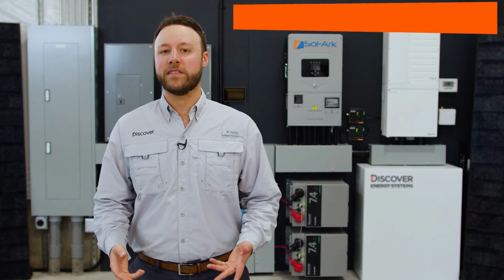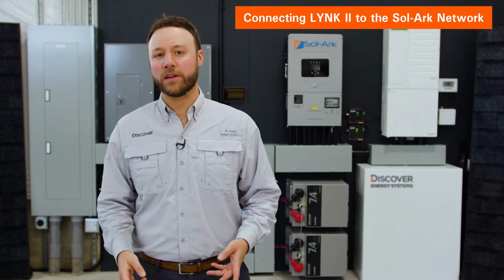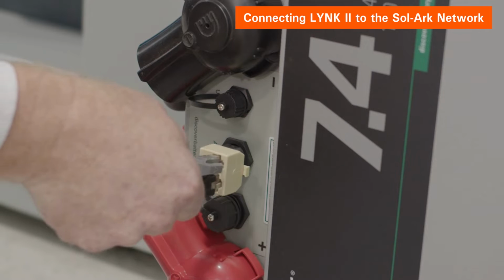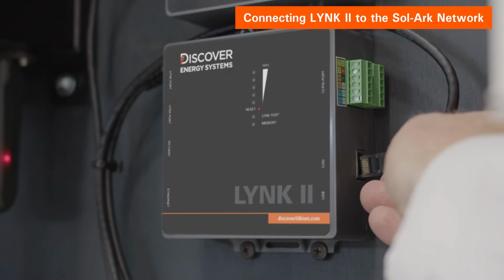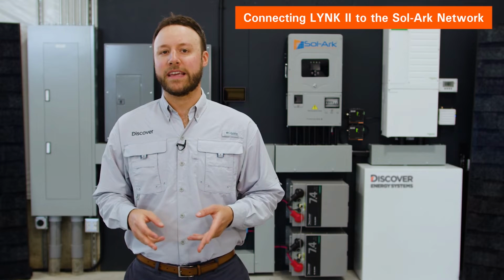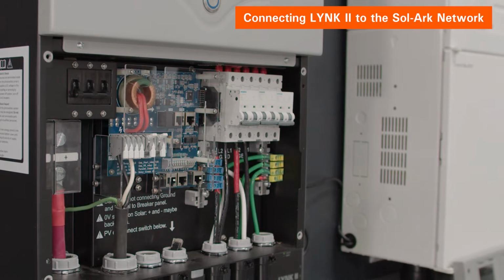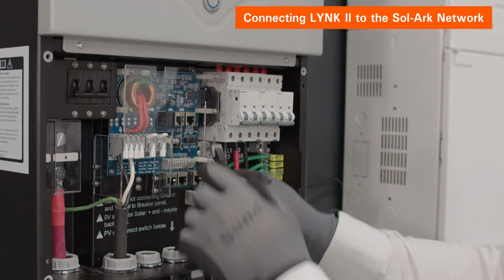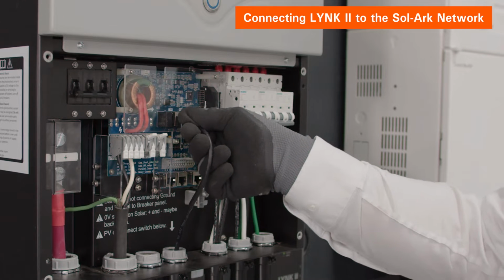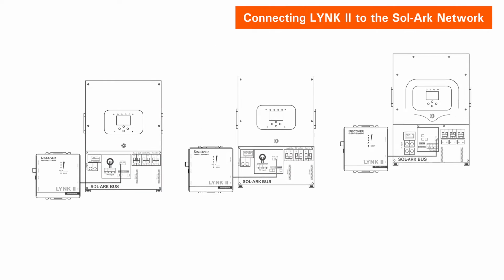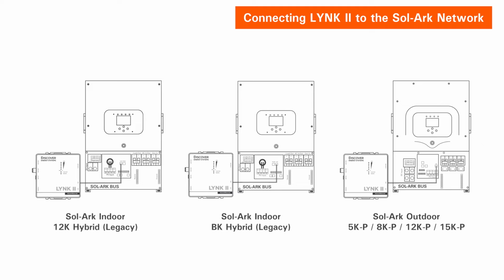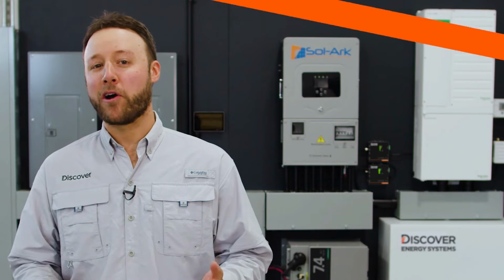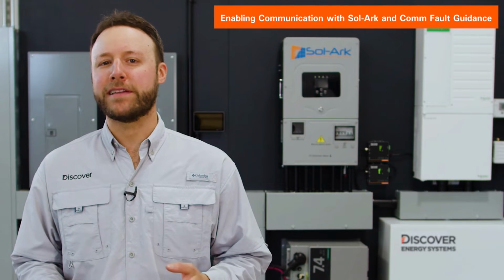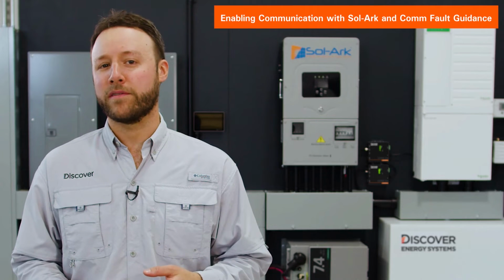Once the CAN out pins of the LYNK II are correctly configured, the Discover Lithium battery can be connected to the LYNK II using a Cat5 cable. After connecting the batteries to the LYNK Gateway, connect it to the Sol-Ark inverter using a Cat5 cable inserted into the correct CAN port. Note that the CAN ports are in different locations on the Sol-Ark inverter depending on the model. Now that the hardware is installed, you can enable LYNK II to communicate with Sol-Ark inverters.